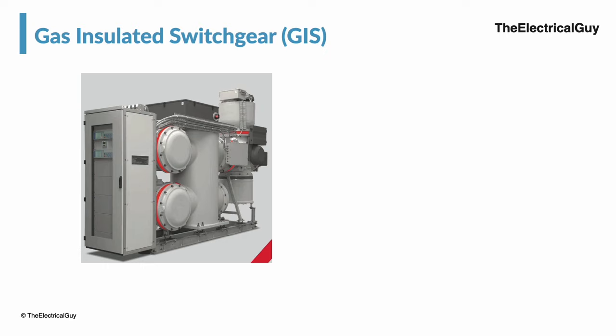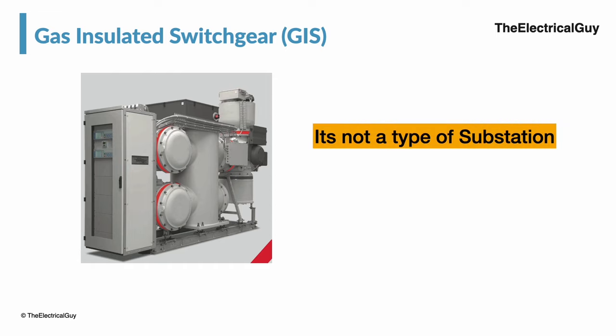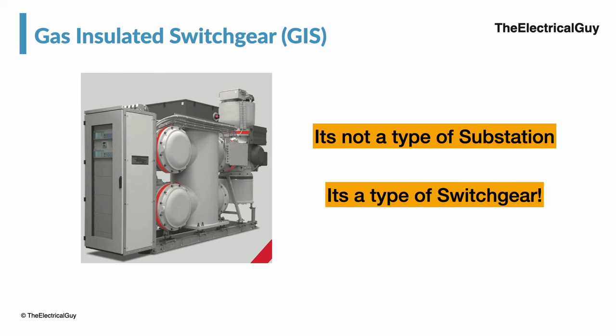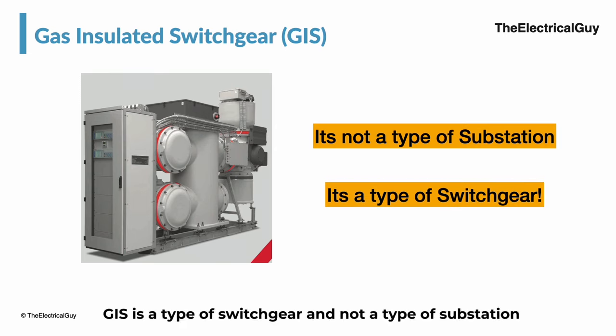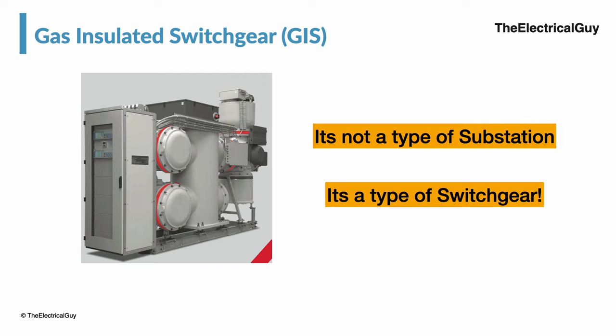First of all, let's make one thing very clear. GIS or gas insulated switchgear is not a type of substation. It is actually a switchgear technology that is used in a substation. GIS is a type of switchgear and not a type of substation. Types of substations are different. But generally, if GIS is used in a substation, then many people refer to it as a GIS substation.